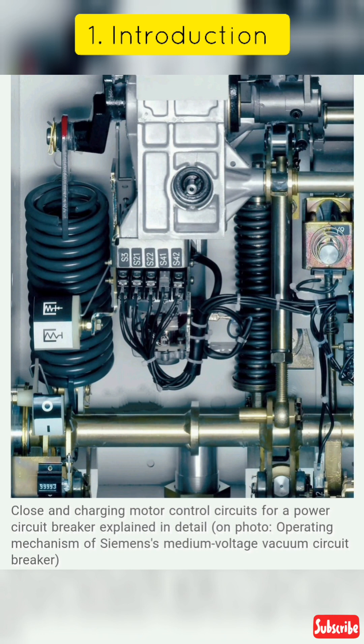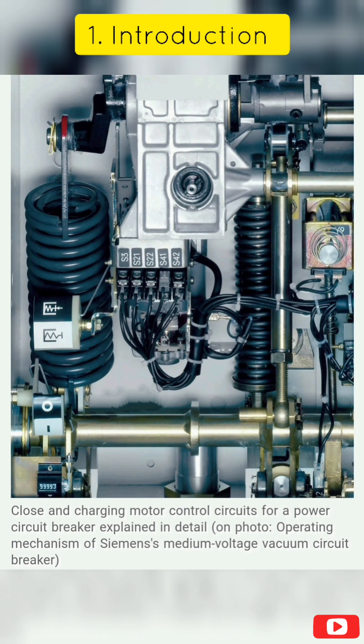The most reliable source in a utility electric generation station is a DC source from a station battery system. Even on a loss of all AC power in the power plant, the battery voltage is maintained and the breakers are able to provide their circuit protective functions.